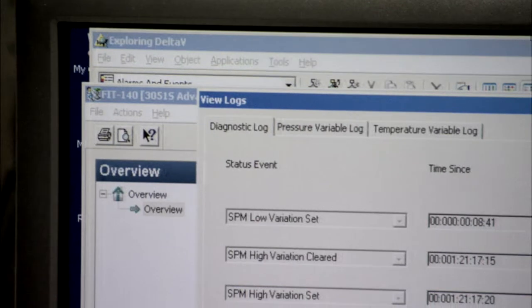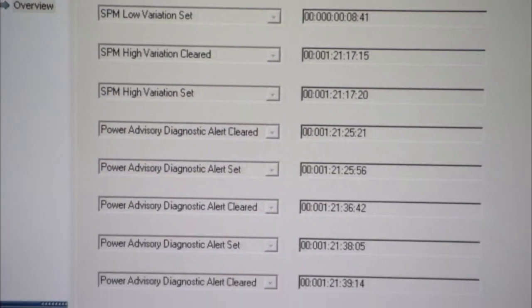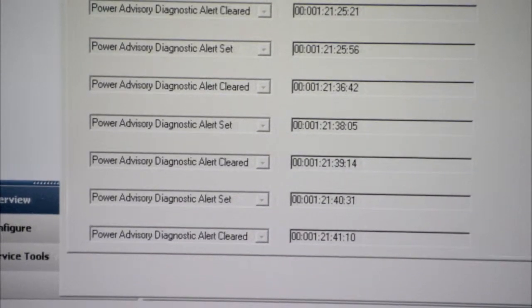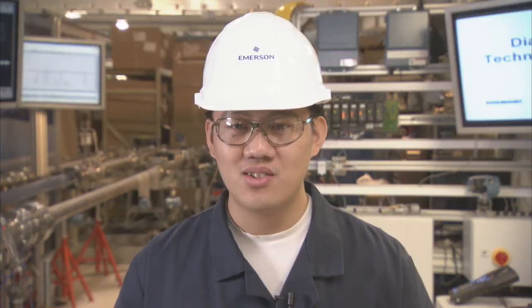One of the features of the 3051S is a diagnostic status log. This is a historical log that will hold the last 10 events that occurred in the device. All the events are time stamped with when it occurred and when it was cleared. This information can be used for device troubleshooting or correlated with events in a data historian, to determine the cause and effect with other devices such as valves or pumps.